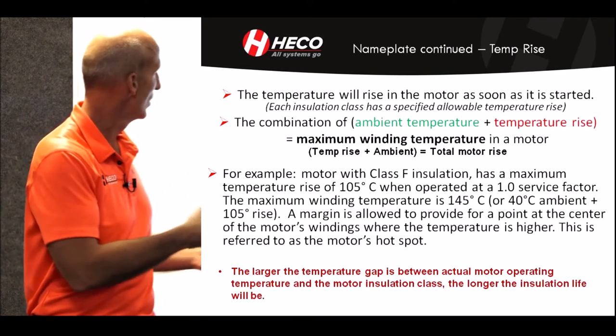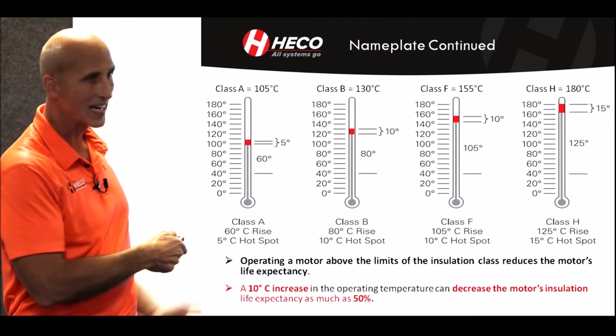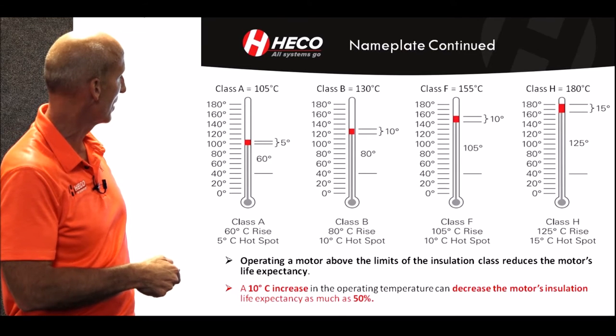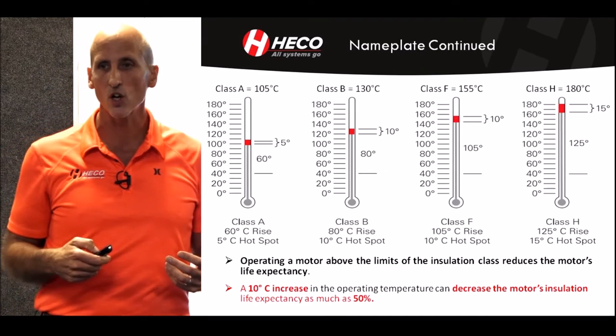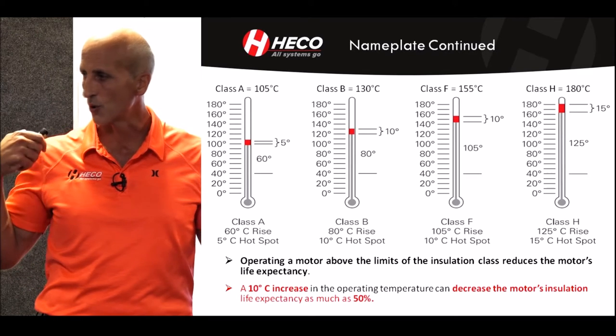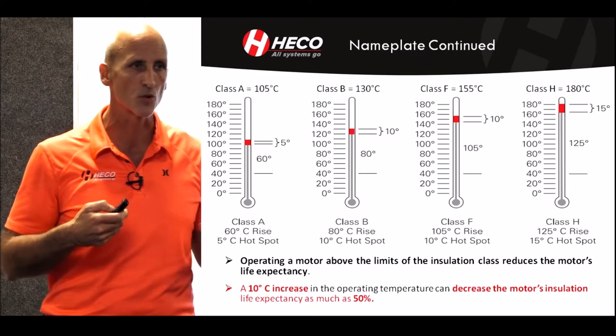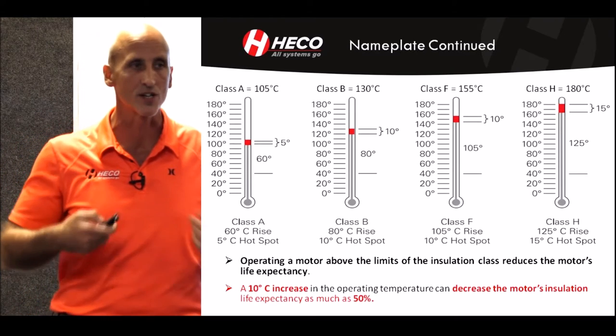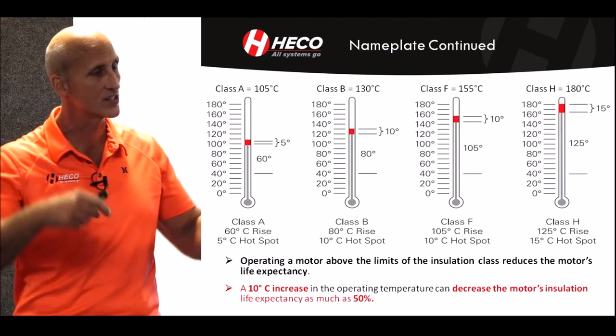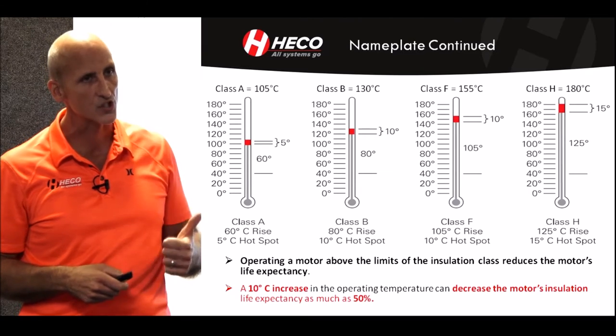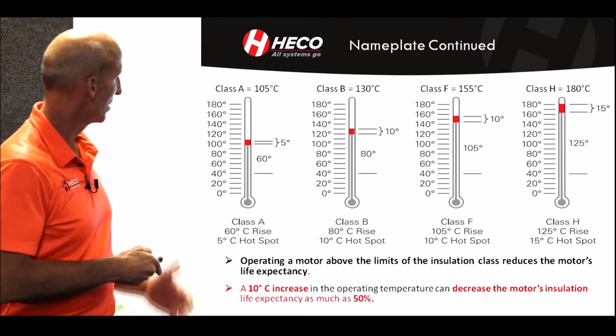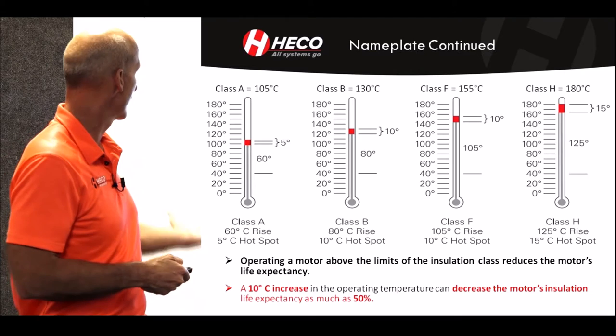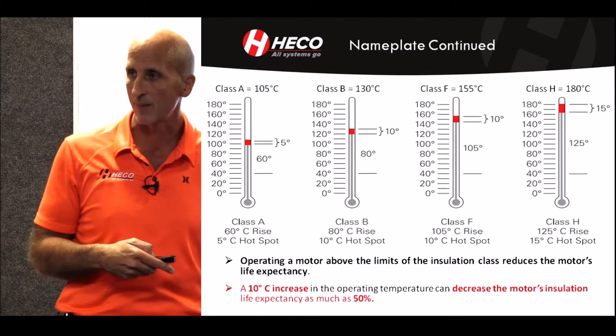This shows how NEMA defines that gap—the hot spot temperature. On a class H, they're giving about a 15-degree margin. One opportunity I look at when rewinding motors is to improve that margin. With many designs, we can actually improve it by increasing the copper cross-sectional area. Increasing the copper cross-sectional area causes the temperature to go down and also slightly increases the efficiency. For every 10 degrees C increase in temperature, you decrease the winding life by 50%.